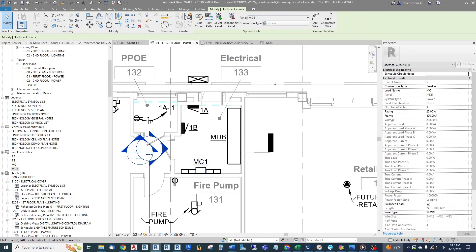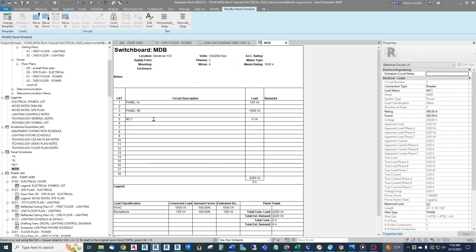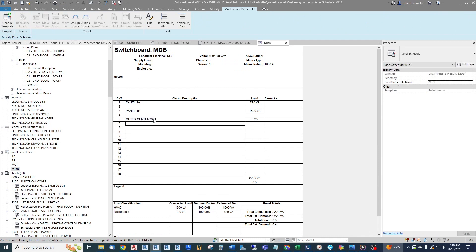Same way — you see the pattern — connect to MDB. We don't know the exact size yet, so let's call it 400 amps for now as a placeholder. Unless you've done preliminary square footage sizing, you won't have a good feel for that yet. That is now connected to MDB. Looking at the schedule again, there are our three loads. Let's rename it 'Meter Center MC1'. We don't have anything connected to that yet, but this is simply how we connect panels to switchboards and all the loads get brought in automatically.